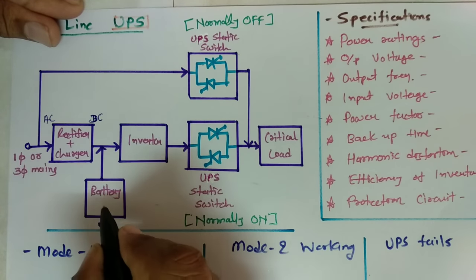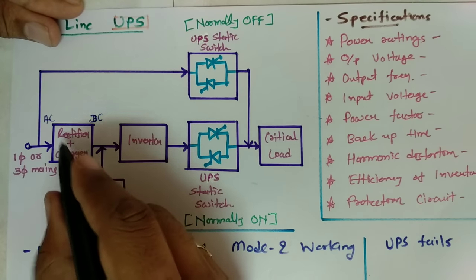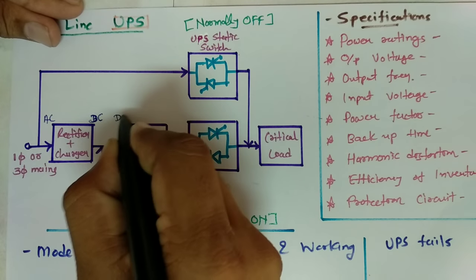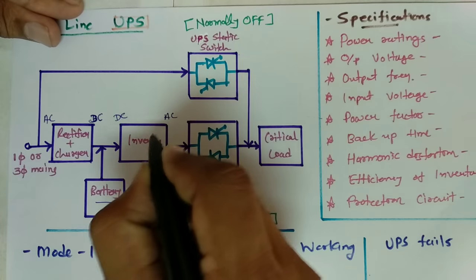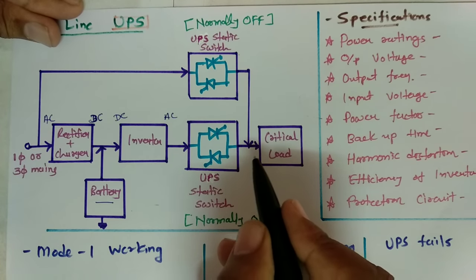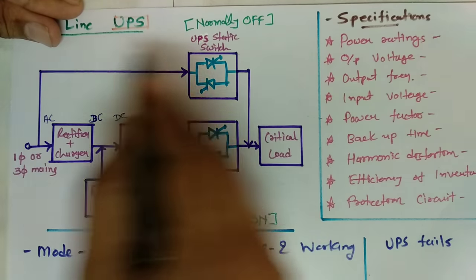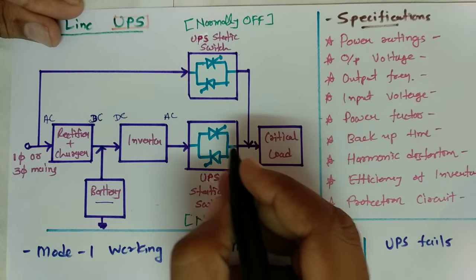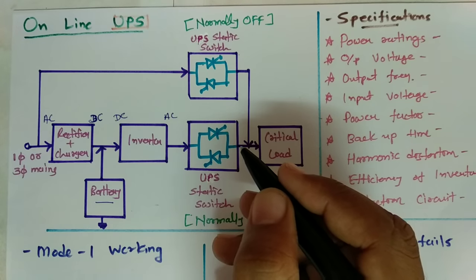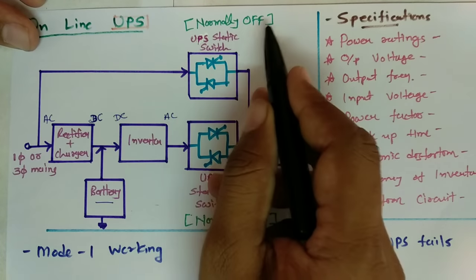This DC signal is utilized to charge the battery. The DC output at the rectifier will also be given to the inverter. The input of inverter is DC, and inverter converts DC into AC, so the output of inverter is AC. Then there is an AC static switch after the inverter, connected to the critical load. Another AC static switch is connected from three phase mains. In online UPS, the switch after the inverter is normally on, and the switch from mains is normally off.